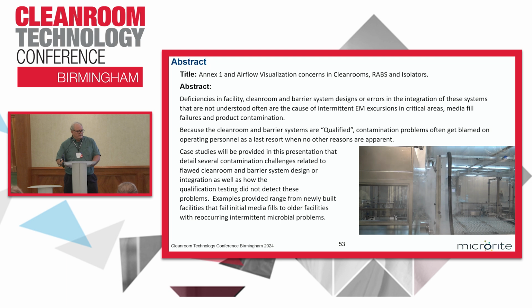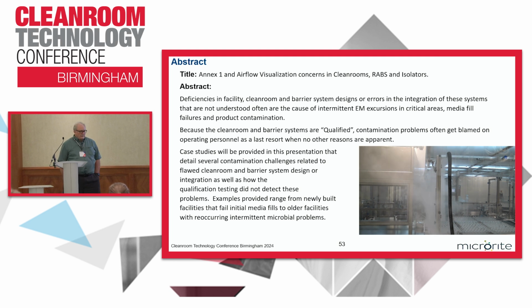My abstract is really talking about the difficulties in facility, cleanroom and barrier system design, or the integration of cleanrooms and barrier systems, all of which can affect our airflow and lead to sometimes intermittent environmental monitoring excursions in critical areas, sometimes intermittent media fill failures, and product contamination. And because the cleanrooms and barrier systems are qualified, contamination problems often get blamed on operating personnel as a last resort to get things running when there are no other reasons apparent.